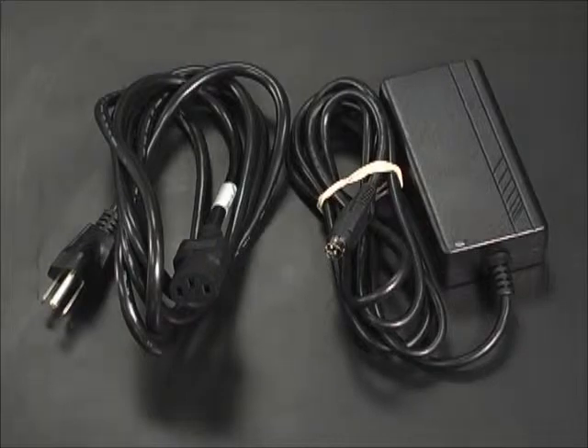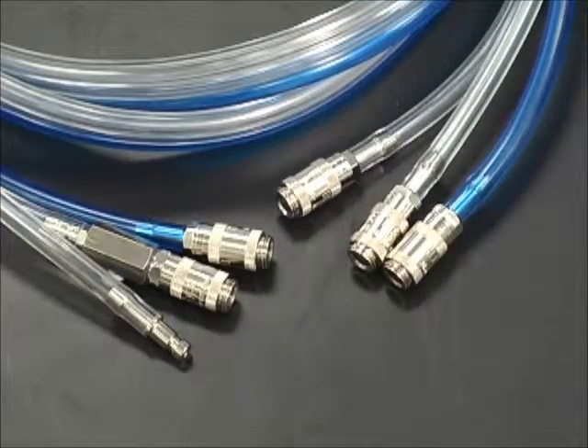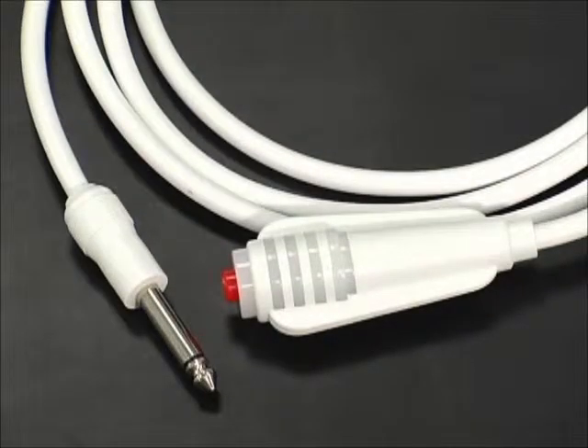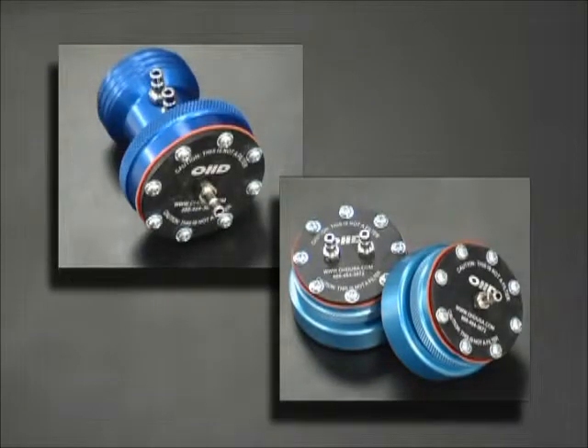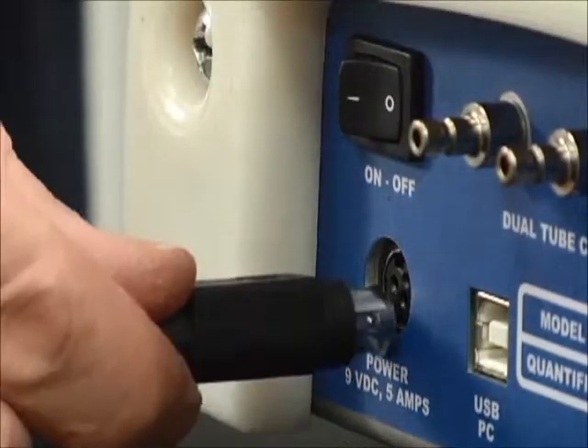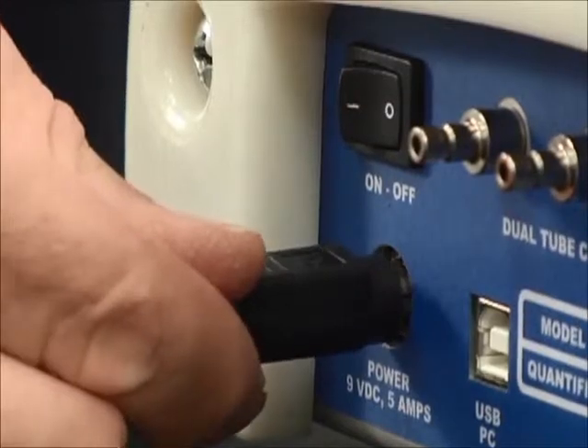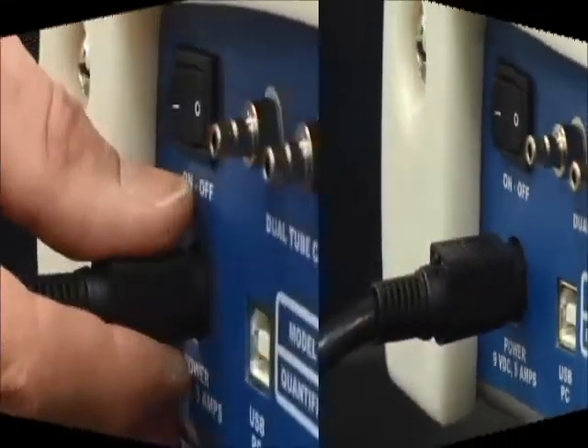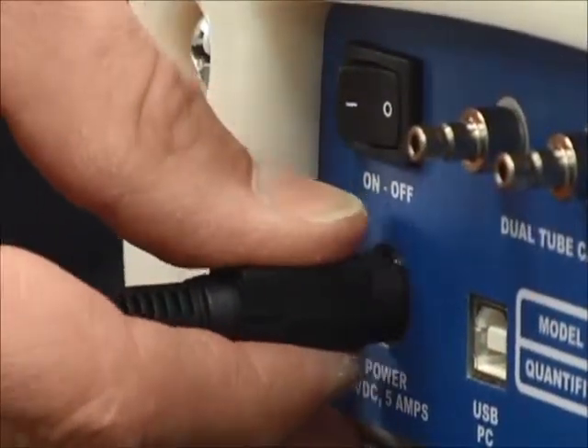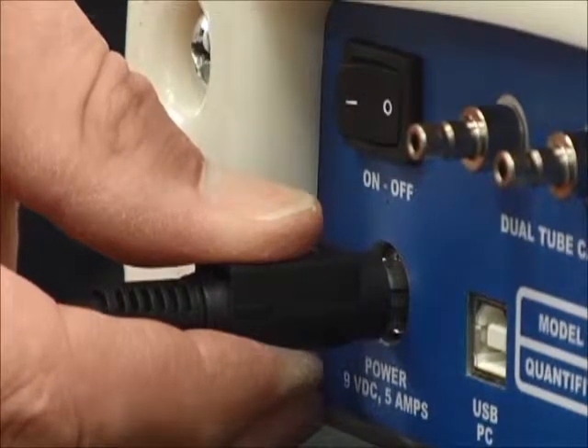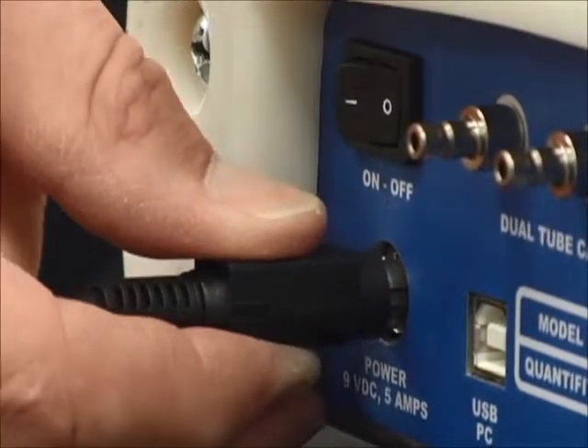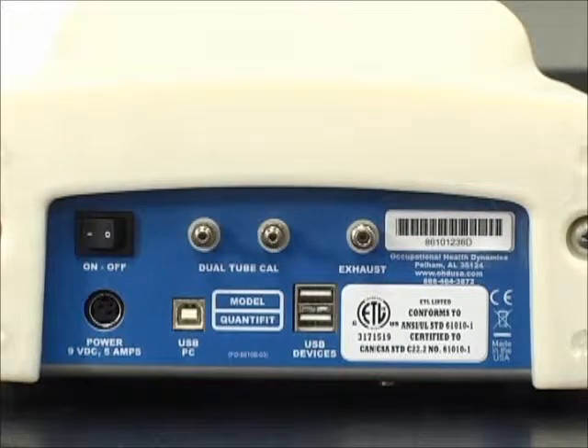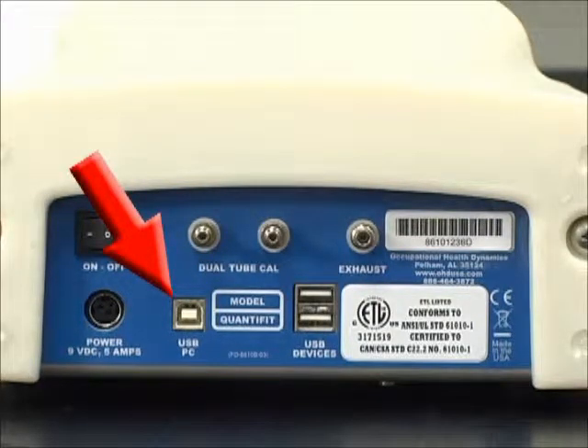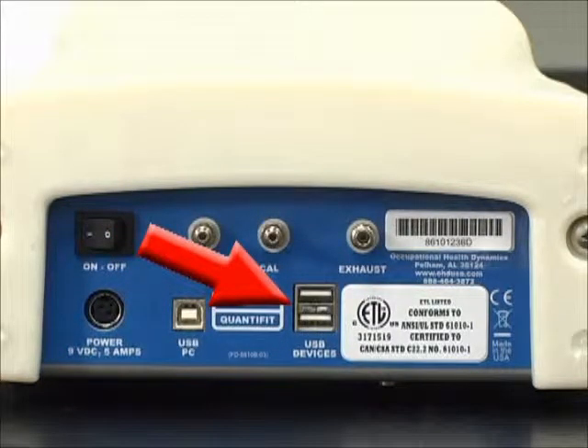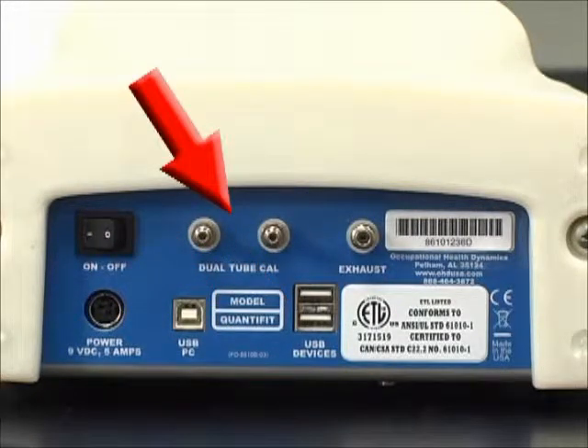You'll need the power cable, the triple hose assembly, the white trigger button, and the fit test adapter. When inserting the power supply, the flat side should face up. When removing the power cord, you must pull on the portion with the flat top in order to release the cord lock. On the back of the instrument, you will also find connections for PC interface, USB ports for keyboard, printer, and memory stick, and calibration ports.